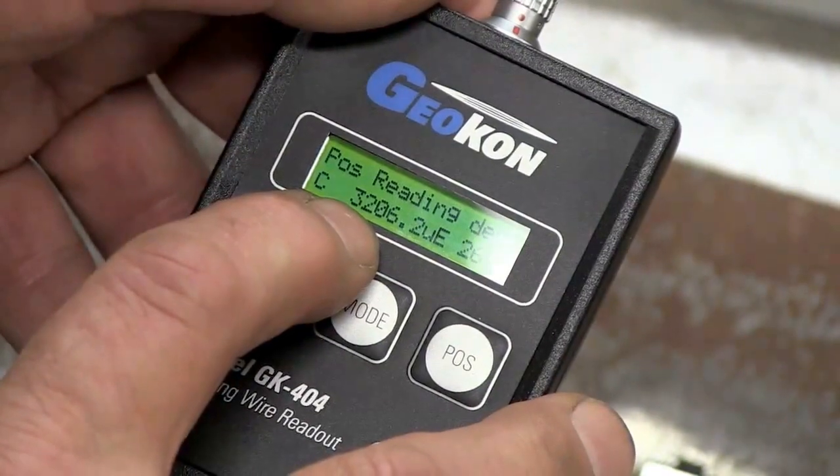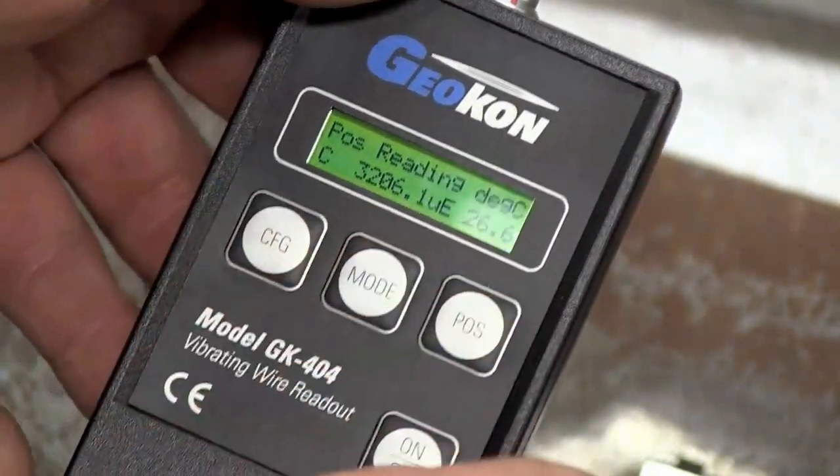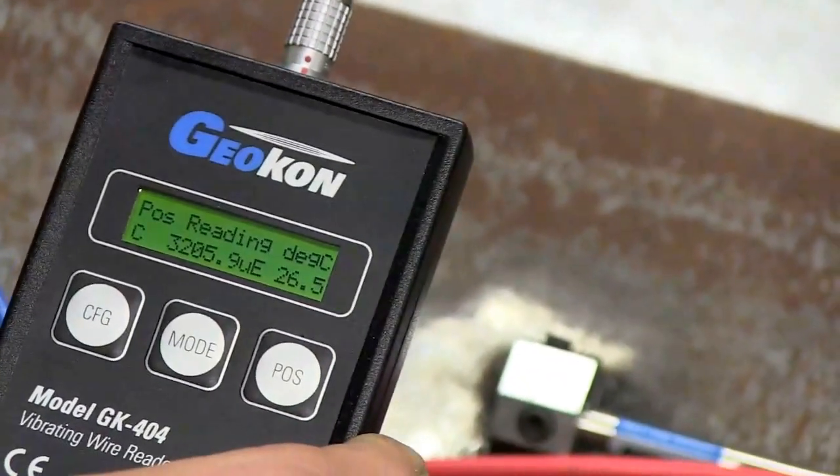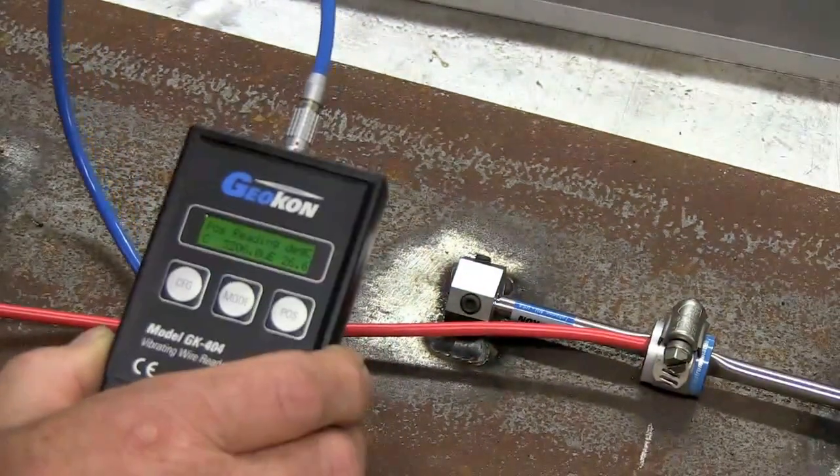The gauge comes from the factory pre-tensioned at about 3,000 microstrain. This is reading 3206. 3,206 microstrain. For a mid-range position, it's about 2,500 microstrain for this gauge.